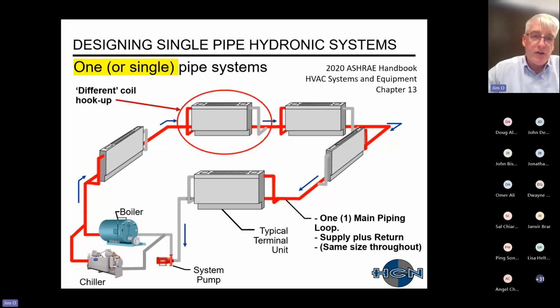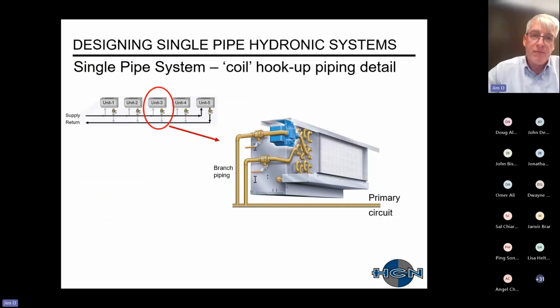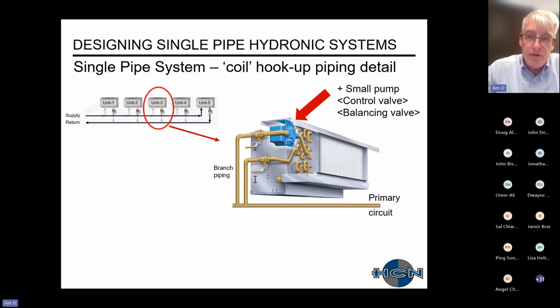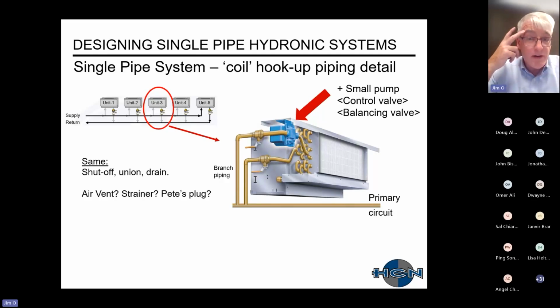You have a different coil piping hookup from before. So with the single pipe system, here's a detail showing the piping detail at the coil or your terminal unit. What you've done is you've added a small circulating pump, and you've removed the control valve as well as the balancing valve. You can see the primary circuit, and then there's your branch piping where that's located. What is the same as before is your shutoff valve. You should have a union for isolation, a drain, air vent, etc.